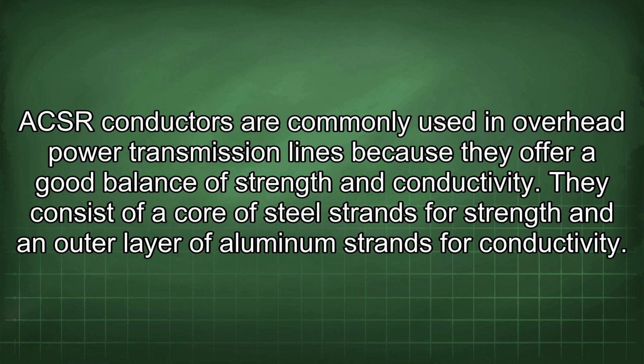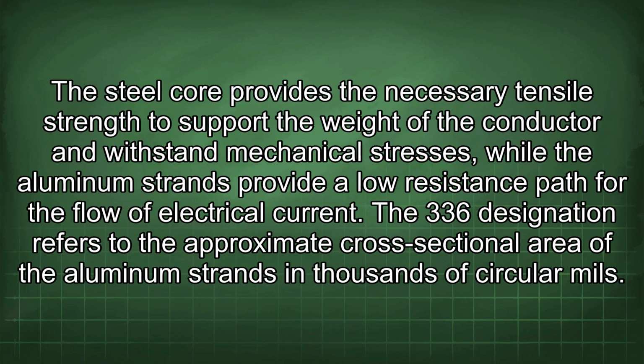and conductivity. They consist of a core of steel strands for strength and an outer layer of aluminum strands for conductivity. The steel core provides the necessary tensile strength to support the weight of the conductor and withstand mechanical stresses, while the aluminum strands provide a low resistance path for the flow of electrical current.